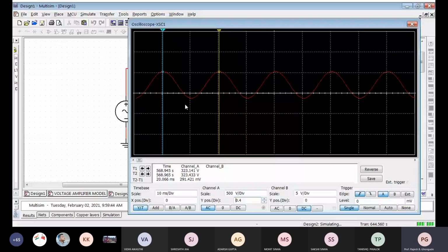It's nearly 1.2, not 1.25 also. Maybe slightly here and there, but fine. So you will get the same kind of value. But you can see here that if I go on increasing, this is 1 kilovolts. So your accuracy of measurement will also decrease because the resolution is now a little bit poor.